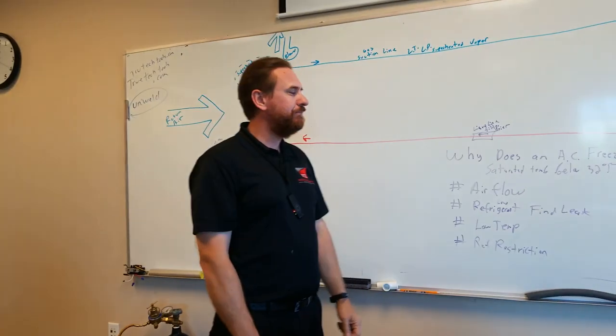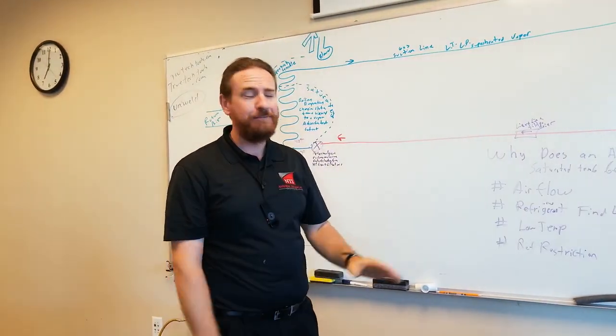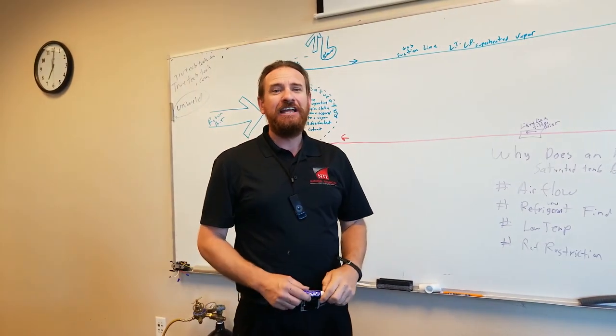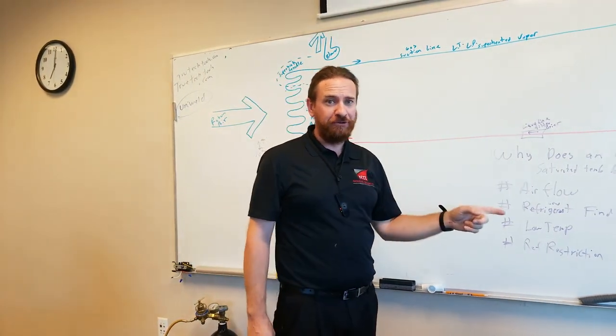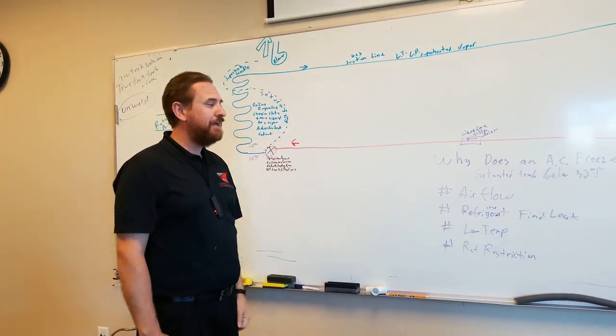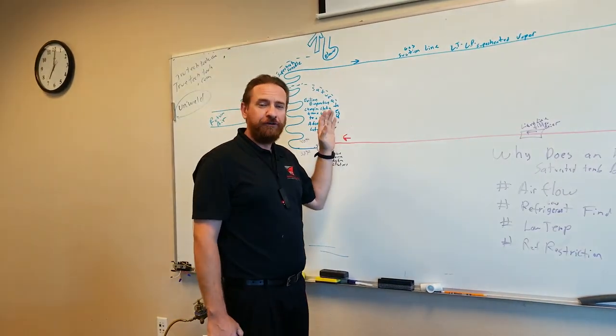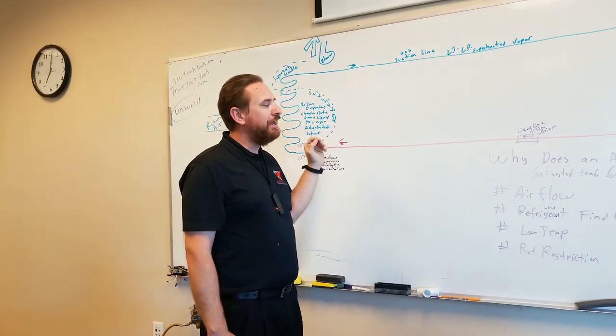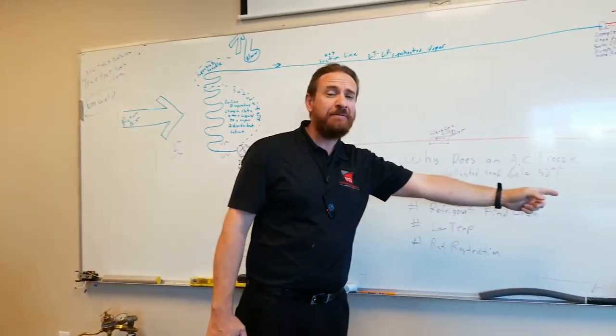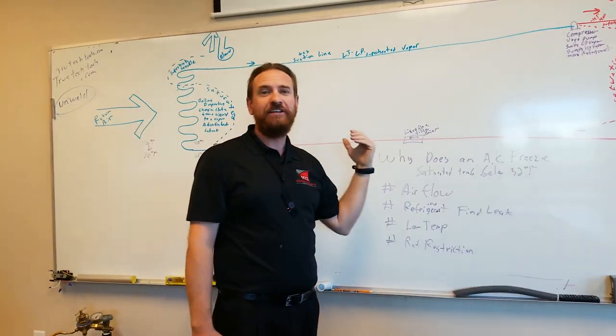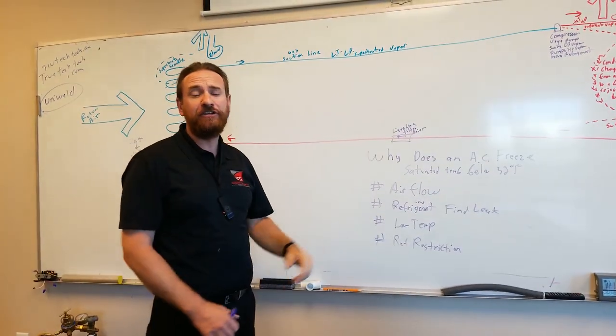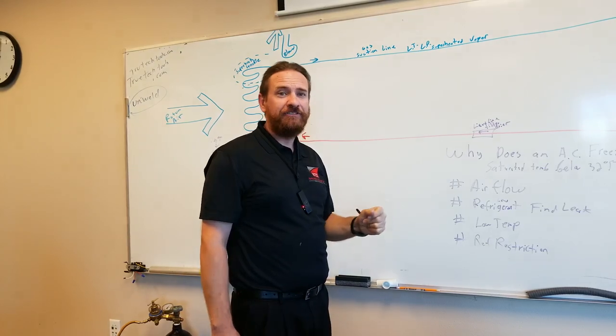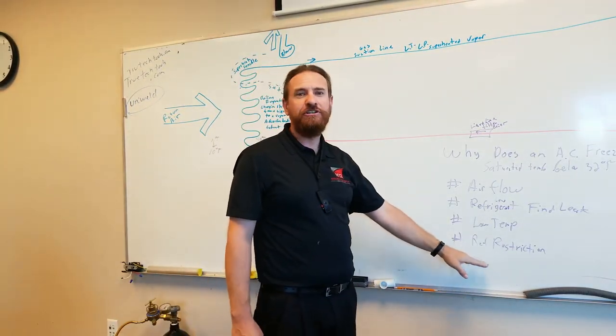So when a system is freezing up — saturation temperature below 32 — immediately think airflow and eliminate that first. After de-thawing the system, check the refrigerant charge via superheat and subcooling. If it's a TXV, focus more on subcooling but still check superheat. If it's a fixed orifice, focus more on superheat using indoor wet bulb, outdoor dry bulb, and the formula or chart or app — and still check subcooling. If the charge is low, you have a leak. Also, temperature inside or outside too low is quick to identify, and refrigerant restrictions can usually be found with a thermometer.